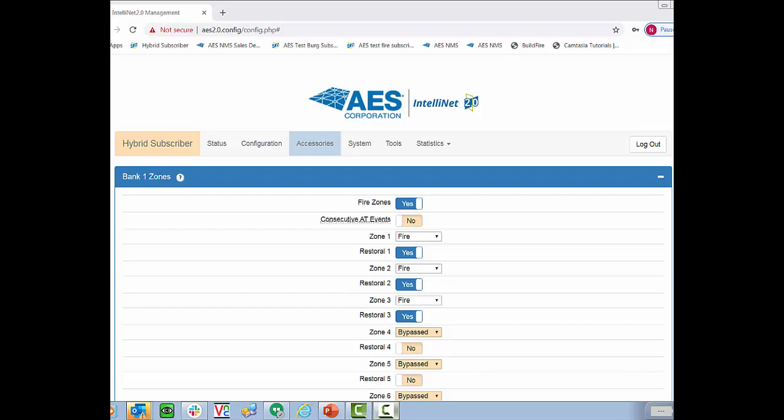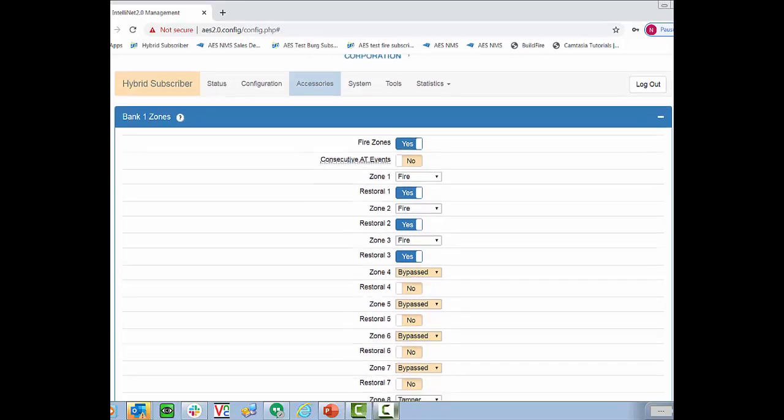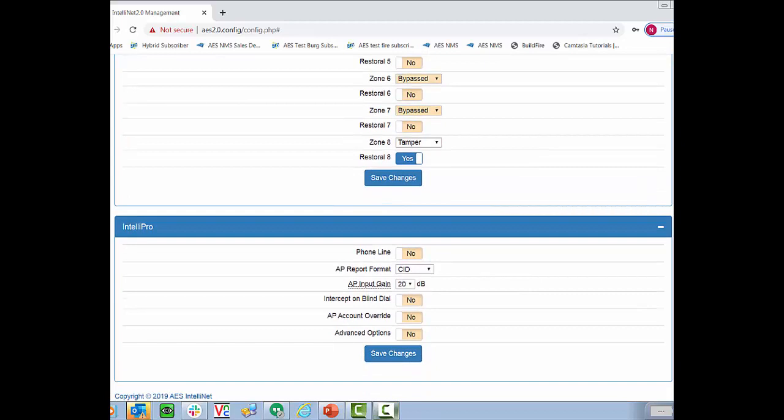If you're going to connect our subscriber using the fire alarm panels dialer, what you need to do is scroll to the bottom of this screen where you'll see our Intellipro menu. One of the main features I want to show you today, and we are going to do a whole video on programming the Intellipro, is the AP account override flag. Right here. If you have a fire alarm panel that it's hard to gain access to, like a simplex panel, or something like that, and the AP report format is already set to CID, what you can do is select this flag, and it will overwrite the account ID from the fire panel with the subscriber ID programmed into the AES subscriber before passing it along to the central station.